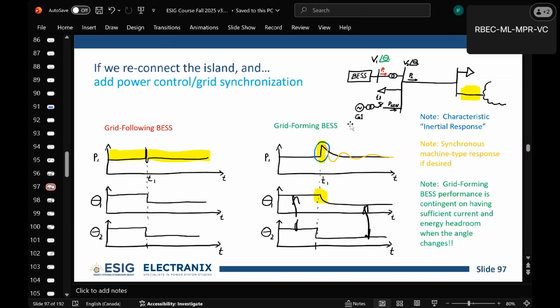And that's basically grid forming. If you take nothing else out of this course, that's how grid forming works. Everything else is just going to be details: how to limit current, how to do different types of controls afterwards and deriving benefit, and all of that. But if you want to know what people mean by grid forming, whether it's in an island or not, microgrid or not, synchronized, that's what grid forming is. So no more discussion about nobody even knowing what they mean by grid forming, right? We know. It's this. That's all it is.